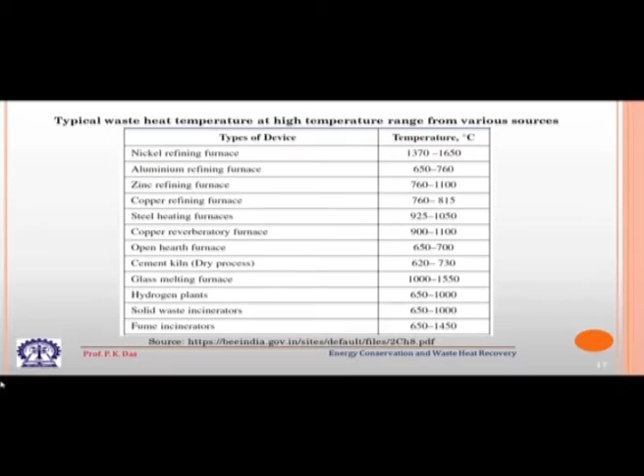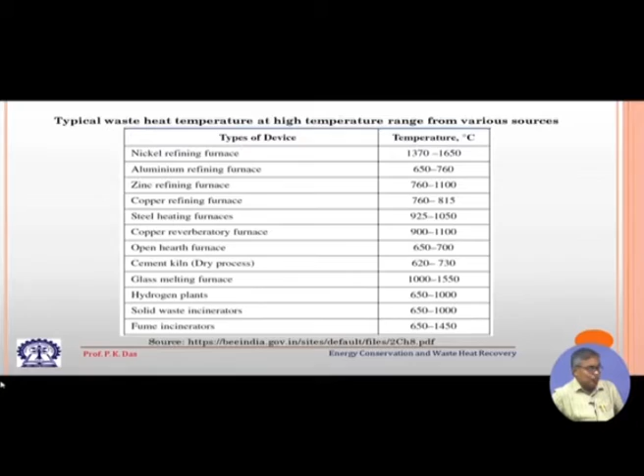Like the first one, the nickel refining furnace, its temperature could be as high as 1650 degrees Celsius. So, you see this is good enough for some sort of power cycle. This is good enough for generating electricity using a usual thermal power cycle. One can easily have a gas turbine or steam turbine plant using these kinds of sources. But again one has to keep in mind that this is only the temperature. The amount of heat we are getting, or the total mass flow rate of exhaust gases, is also important for designing the waste heat recovery system. If we want to design a thermal power plant out of this waste heat gas, the amount of gas coming out is also important. Sometimes these gases are dirty, which we also have to keep in mind.